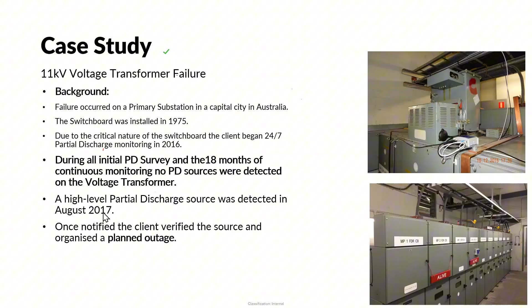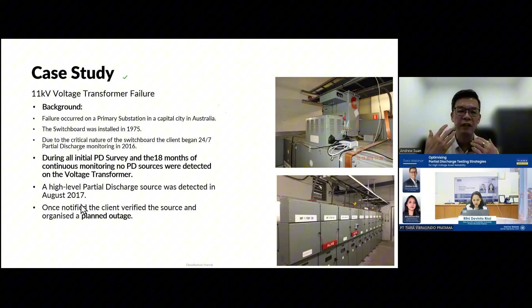However, in 2017, it actually started to have PD. The owner is very lucky because when we started 24/7 monitoring in 2016, and then in August 2017, the first PD that was generated was immediately captured by the permanent monitoring system, because the system was polling for data every 2 minutes. So once there's something, 2 minutes later, it will start the PD survey again. Eventually, it was the first to detect, so it sent an alert.